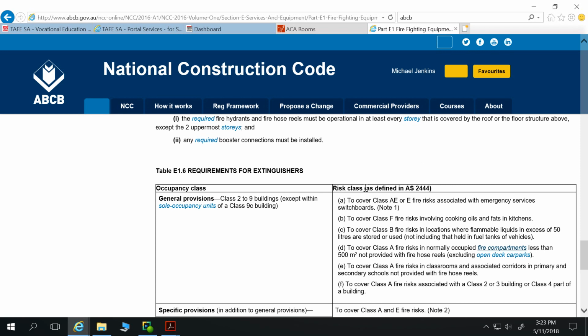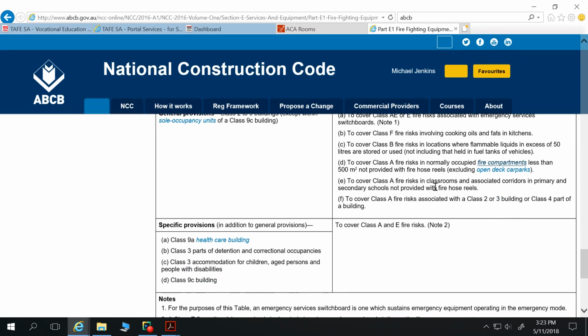So let's have a look at AS 2444, and actually we'll have a quick look at AS 2444. But basically, you're going to want to have that fire extinguisher close to a doorway, close to an entry within that kitchen area. So if a fire happens within that kitchen area, someone can go to that door, grab the fire extinguisher, and put it out. So it has to be in an easily accessible location, clearly visible, and also a little bit separated from where the fire incident is going to happen.